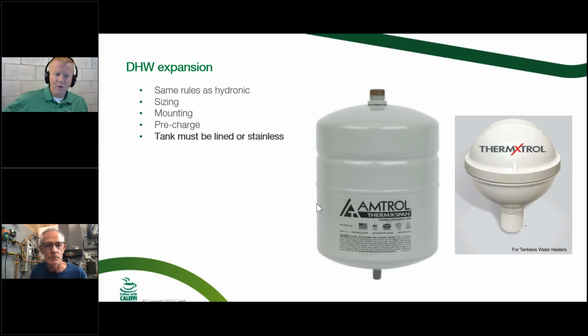The other big one that a lot of people don't really think about is anytime you have a closed system on your potable side, meaning all the faucets are off and you have a backflow preventer in there. That's a closed system. Then at that point, if all the fixtures are off, you need to be able to accommodate any temperature increase or decrease with an expansion tank like this.